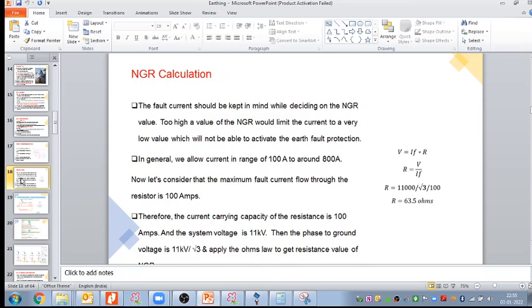This is what we discussed. NGR calculations, we have already discussed the NGR calculations. The fault current should be kept in mind while deciding the NGR value. Too high a value of NGR would limit the current to a very low value, which will not be able to activate the earth fault protection. So we cannot keep the NGR value too high. In general, we allow current in the range of 100 to around 800 ampere.